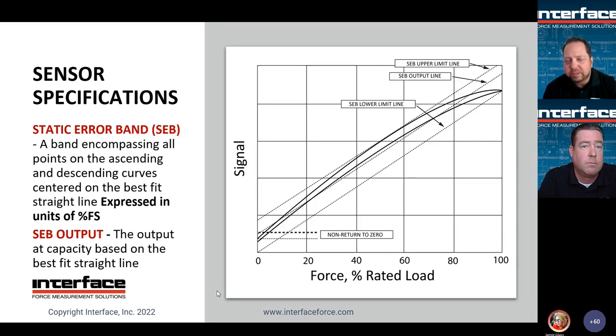So we also provide SEB outputs for our load cells. This is essentially an error band that encompasses the ascending and descending nonlinearity and hysteresis, as well as capturing non-return to zero, and provides a single point output, a best fit if you will, that encompasses all the error for each particular sensor. So it's a way to take the overall performance of a sensor and adjust the rated output for the actual performance of the unit. Instead of just the rated output, you'll have an SEB output, which would end up being the end of that output line, and is typically used if you're doing a single point scaling in your instrumentation.